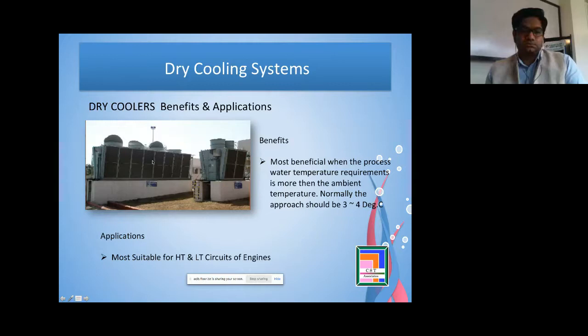Let's say we have an ambient temperature of 45 degrees centigrade, and with a 3 or 4 degrees centigrade approach, we will have a water outlet temperature of 48 to 49 degrees centigrade. That is quite good for the turbocharger. If we go to a higher temperature, the fuel consumption of that engine becomes more, because the density of the air will change.